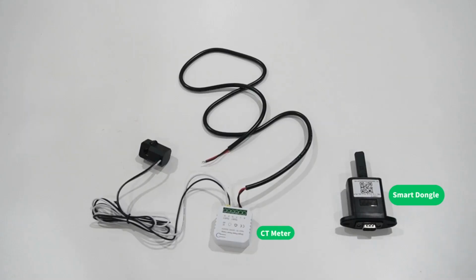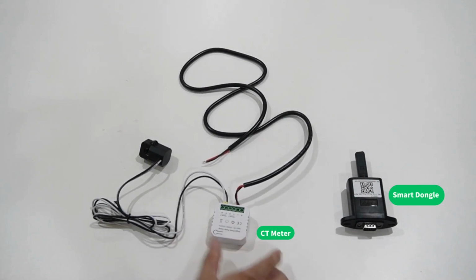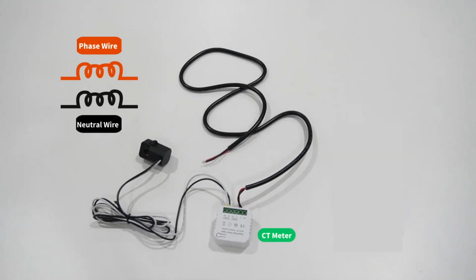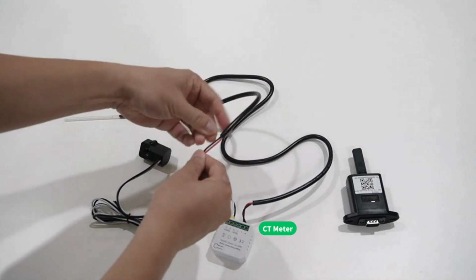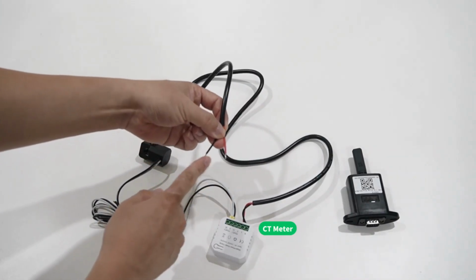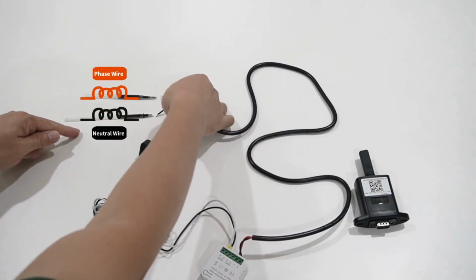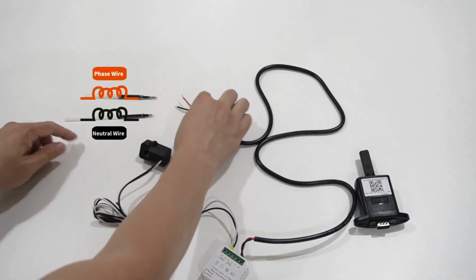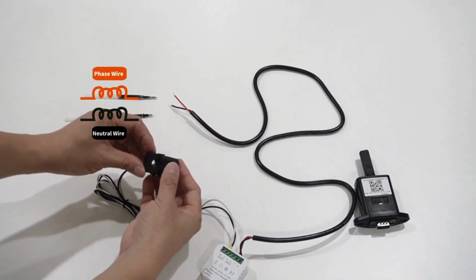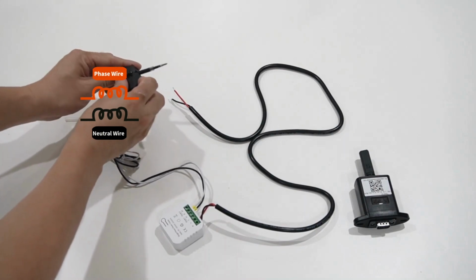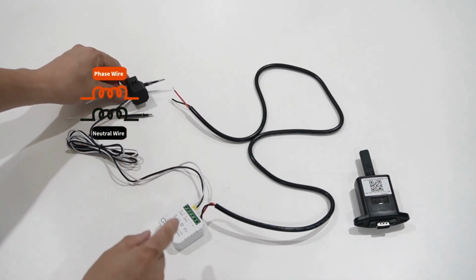The diagram below illustrates how to connect the CT meters to voltage measurement power lines to the inverter. The CT meter requires a conversion cable to connect to the inverter's two power lines. The black cable line of the CT meter connects to the neutral wire of the inverter, and the red cable line of the CT meter must connect to the phase wire of the inverter. There is also a clamp attached to the phase line used to measure voltage and current on the power lines to calculate the energy consumed.